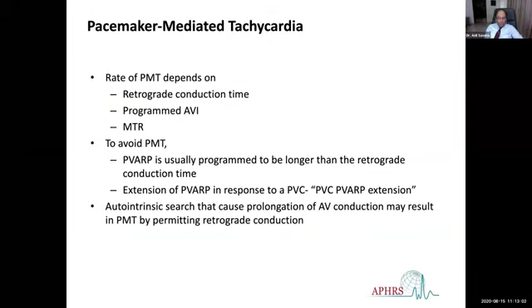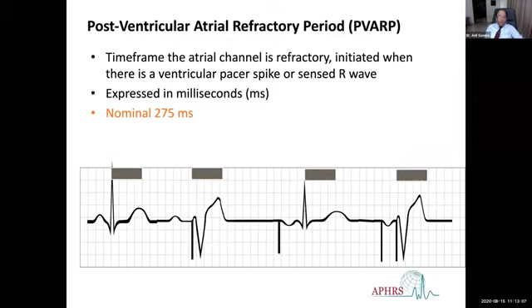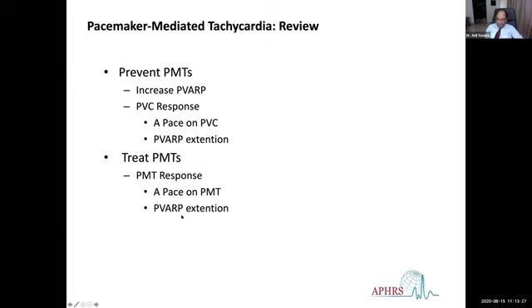Ma. And the pacemakers now have an algorithm which gives an extension of PVARP in response to a PVC, which is called PVARP extension. So every time the pacemaker senses a PVC, it can do one of two things. It can either give a PVARP extension or it can A-pace on PVC. And to treat PMT, that is pacemaker mediated tachycardia, it can either give an A-pace on PMT or it can give a PVARP extension. So this is how you program it.